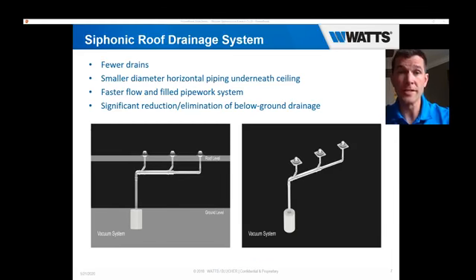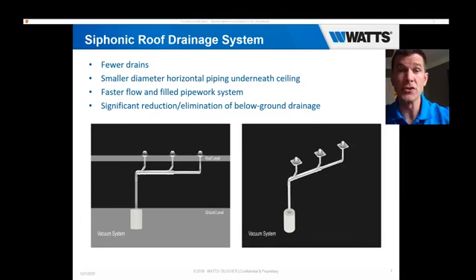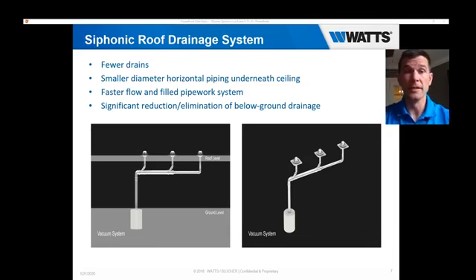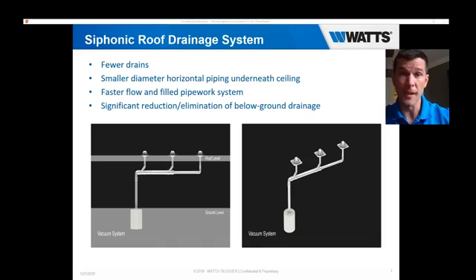Comparing a gravity system to a siphonic system: there are fewer roof drains needed. You're using 100% of the pipe volume compared to a third in gravity, so you don't need as many roof drains to install. You can also use smaller pipe diameters for the horizontal piping underneath. The negative pressure increases flow for a faster, filled pipe system, which is quick due to that low-profile baffle design. This reduces ponding and leads to a significant reduction in potential below-ground drainage — if any — allowing you to run horizontal pipes through the building over to a Watts Rain Cycle harvesting system or divert them to areas more convenient for disposal.